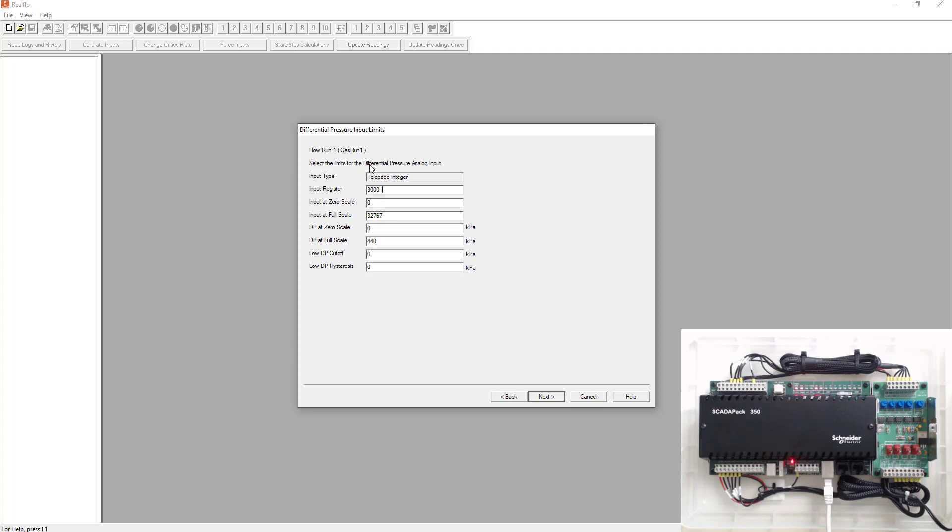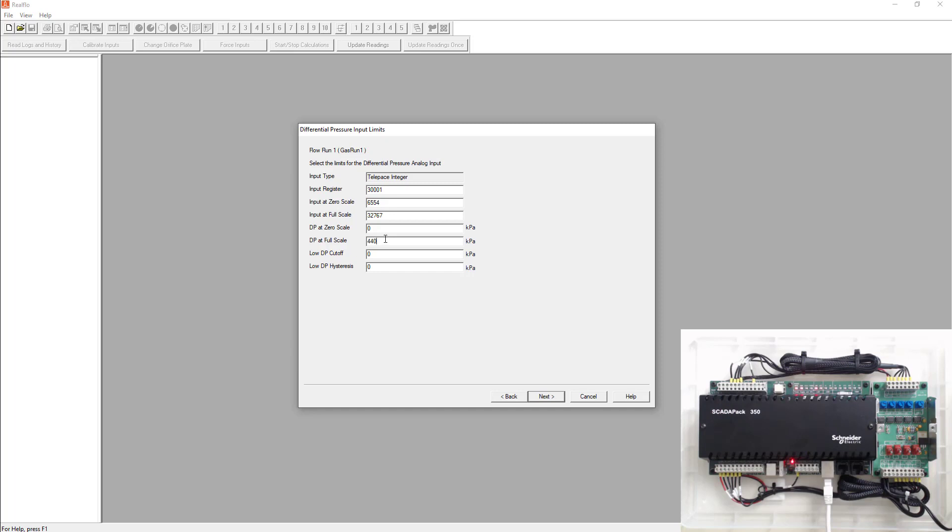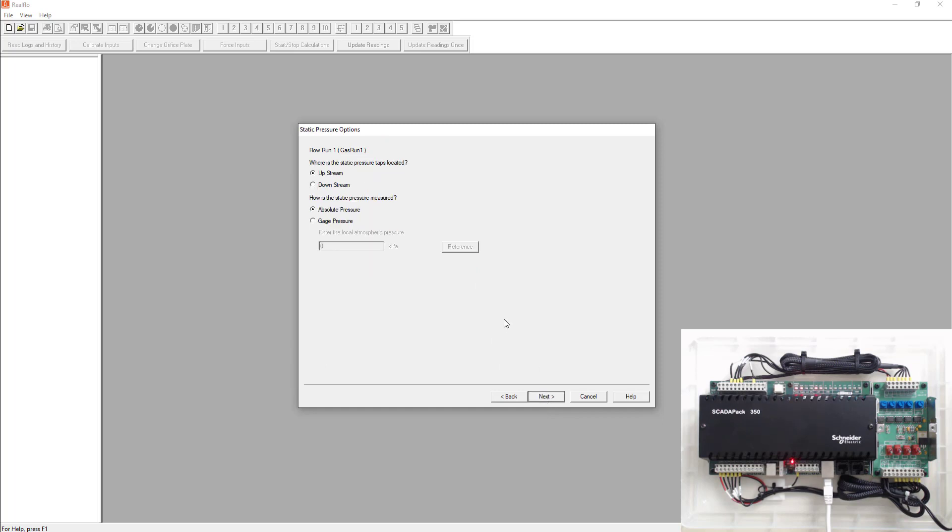We know for our differential pressure is going to be the first analog input. We know that that's register 30001. We know from the previous labs that it's scaled from 6554 to 32767. For this made up differential pressure transmitter, we're going to pretend it's scaled from zero to 440 kPa. We're going to give it a low cutoff of 0.125 and we're just going to leave the hysteresis as is. That's how to set up the differential pressure analog input.